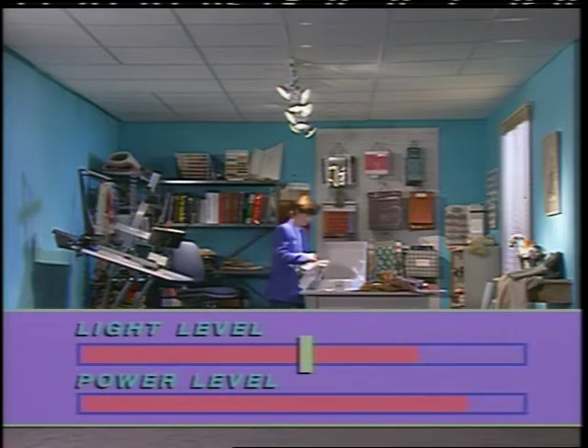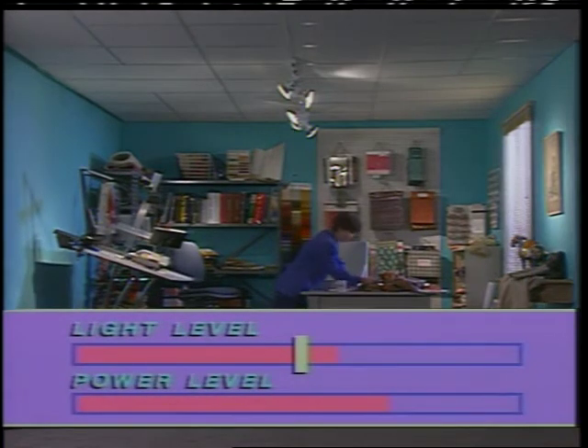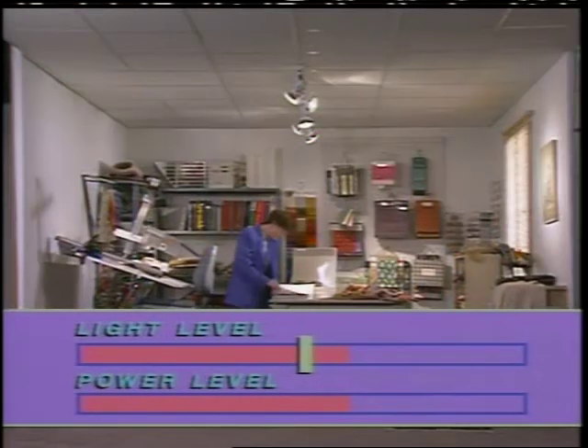By lowering the ceiling, the fixtures are unchanged, but the light level increases. Now, fewer fixtures are needed to meet the designer's requirements and less power is being used. The color and texture of room surfaces also affect light level. By changing the wall color to white, the light level increases, and again, the wattage can be reduced.